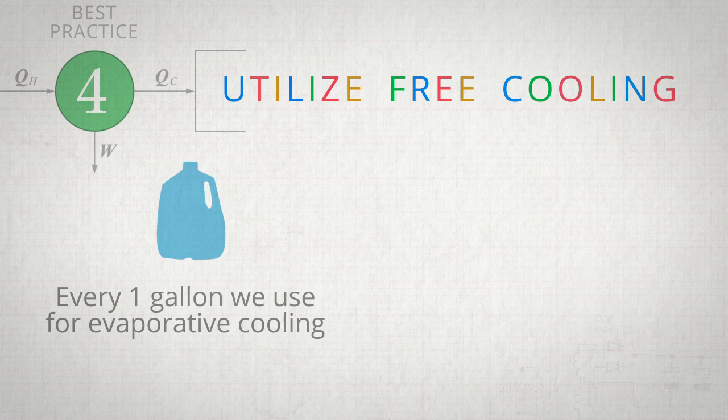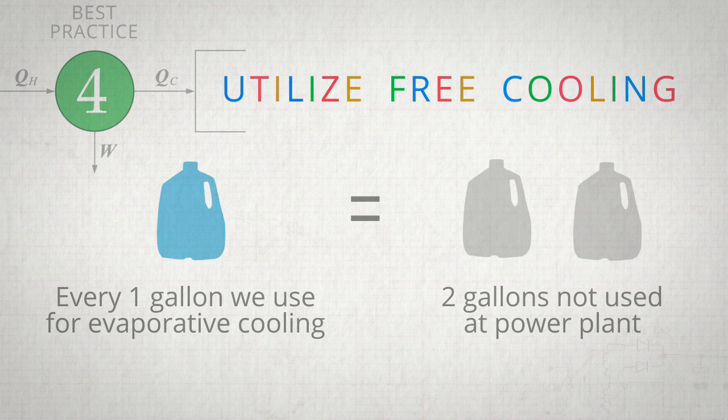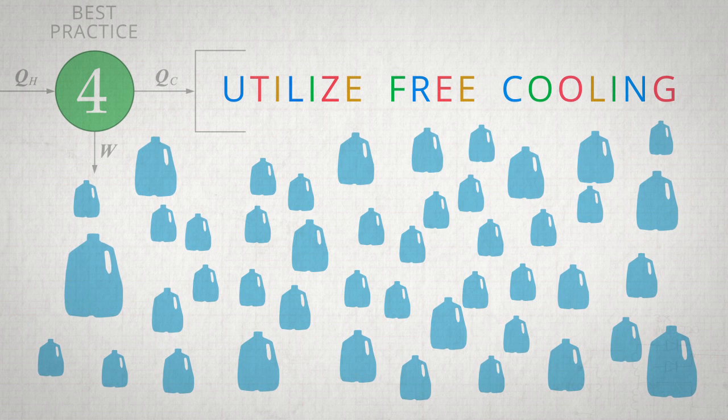Evaporative cooling uses water on site. But what we found through our studies is that by using evaporative cooling in a very efficient fashion, we save water on the whole. For every gallon of water we use in the evaporative cooling plants, we eliminate the use of two gallons of water on the energy production side. This translates into hundreds of millions of gallons per year in water savings.